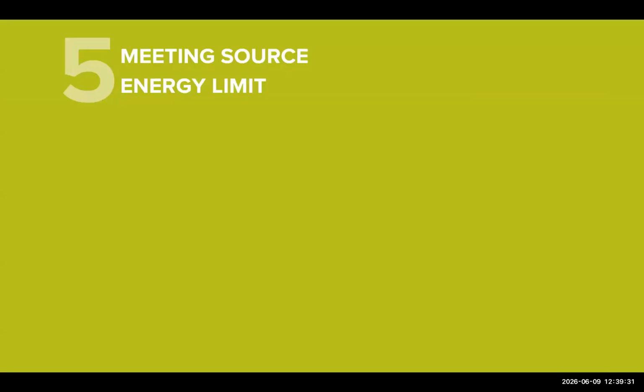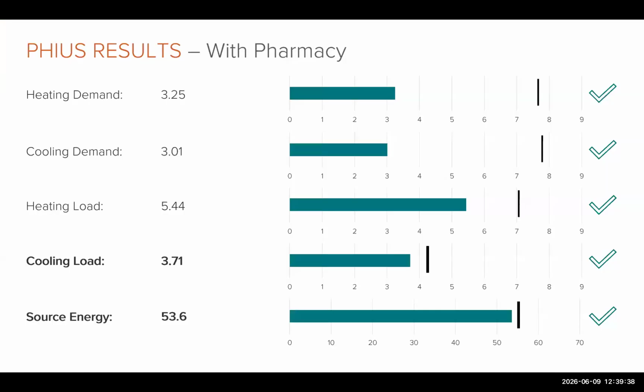Moving on now, I'll discuss the 5 Phius compliance targets and source energy in particular. I'll start by showing how we made out with our overall compliance targets. You need to comply with these 5 limits in order to meet passive house. You can see that we managed to obliterate our heating and cooling demands. We came in well below the limit. We also met the heating load fairly easily. It started getting closer to the limit for cooling load, but we were still okay.